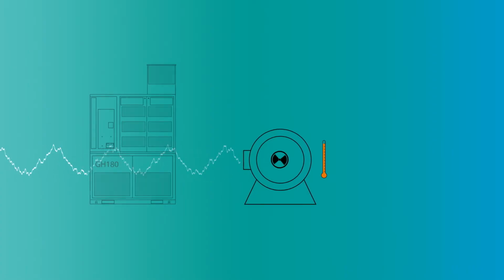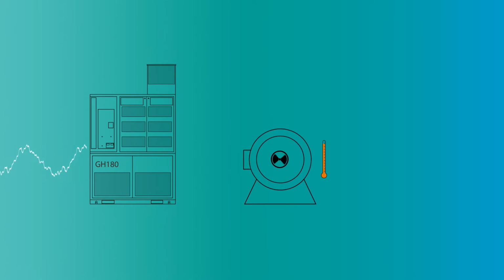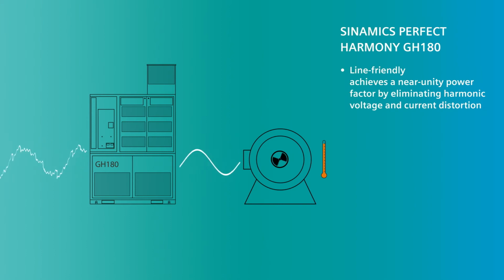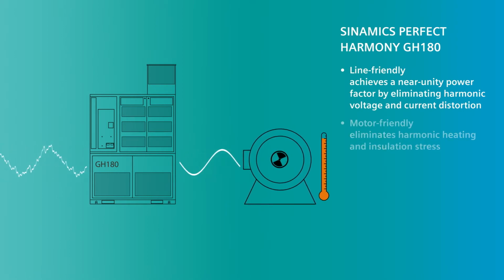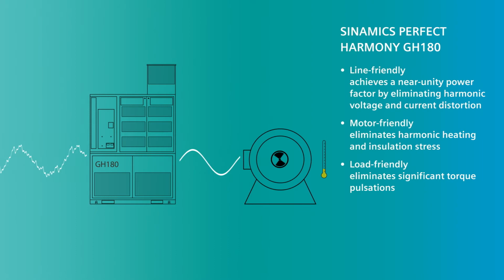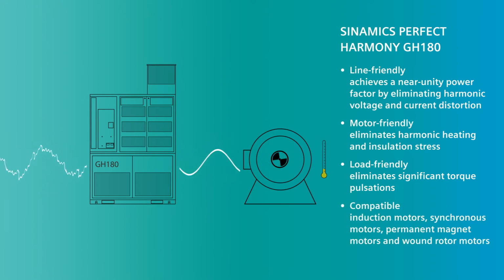The SINAMICS PERFECT HARMONY GH180 converters deliver a waveform output of unparalleled quality, which is line-friendly, as it achieves a near-unity power factor by eliminating harmonic voltage and current distortion. It is motor-friendly, as it eliminates harmonic heating and insulation stress. And it is load-friendly, as it eliminates significant torque pulsations.